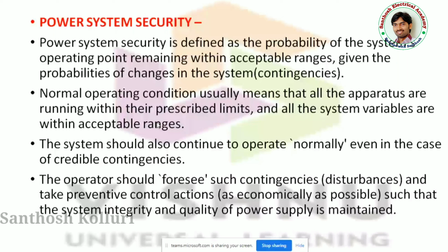It should withstand small disturbances, even though they are happening continuously or consistently. If the disturbance is persisting continuously, then you should switch off, or you should open the circuit breaker. Okay, so the relay has to be set like that. For small disturbances, it should not activate. For long disturbances or continuous disturbances, it should give the signal to the circuit breaker.